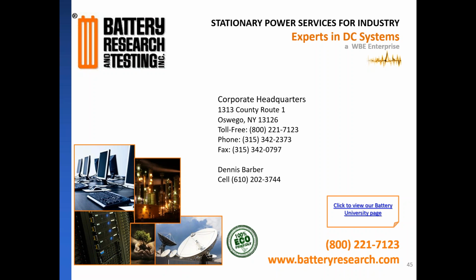So we're going to shoot everything from the breaker on. A lot of these are never going to really see load unless you've been on battery for whatever reason. Now you have a discharged battery and you're going to recharge, and that rectifier is going to current limit. If you have a problem with either the breaker feeding that rectifier or the rectifier itself, and that trips off, now you have a dead battery and a dead rectifier. So full system commissioning testing is getting to be a little more popular.